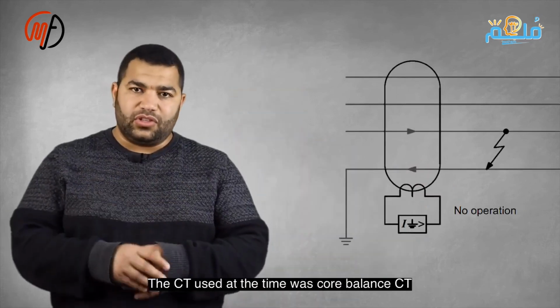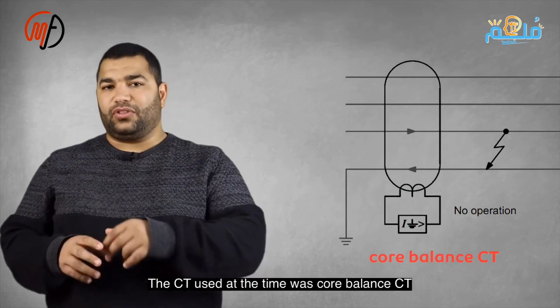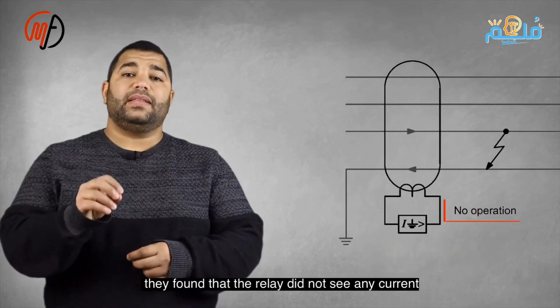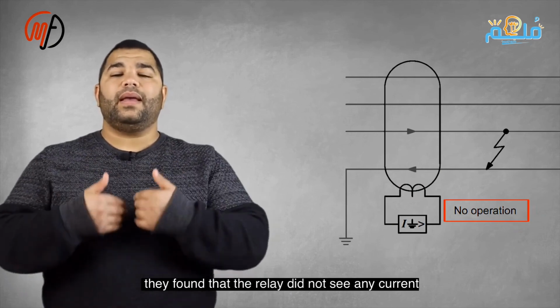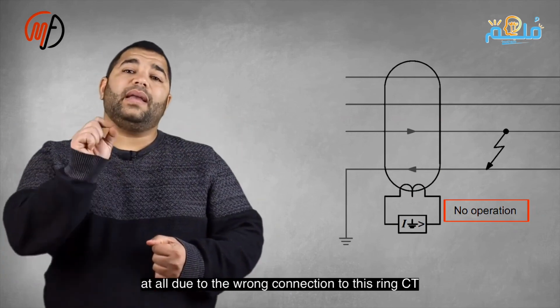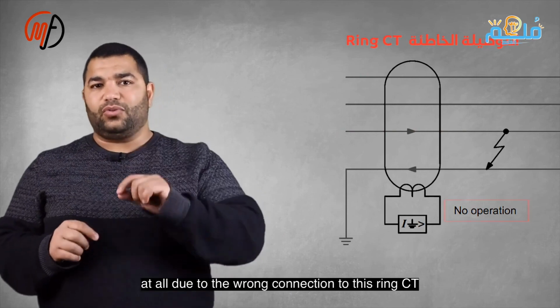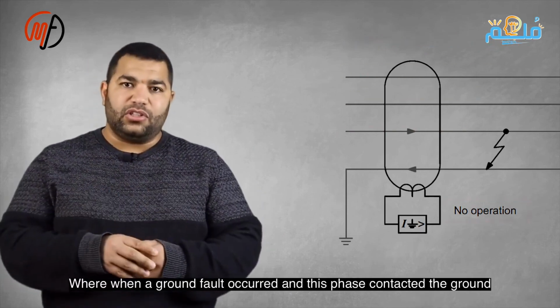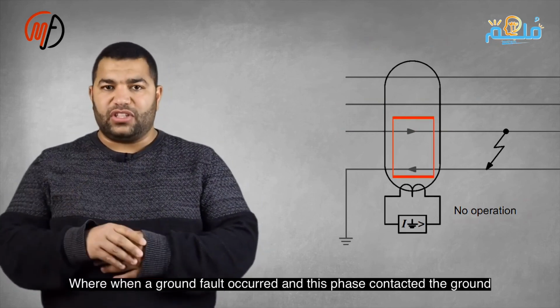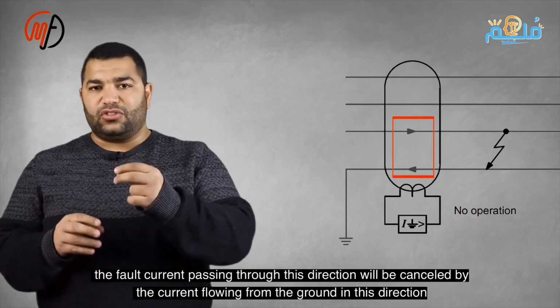When a ground fault occurred, the fault current was cancelled by the return current from the ground, resulting in a 0 directional summation for the relay, an incorrect connection. Fixed by adding a grounding cable to the CT core, the relay detects imbalance and trips the circuit breaker. Issues are common in 3-core cables, so restoring the sheath earth connection is crucial.